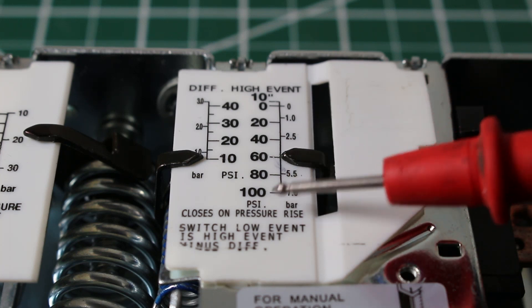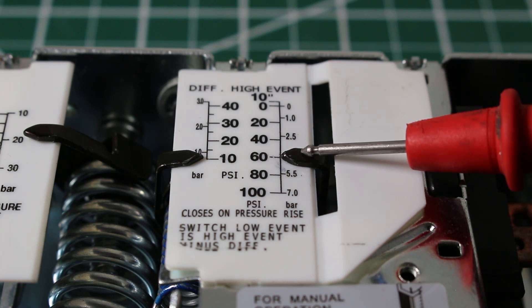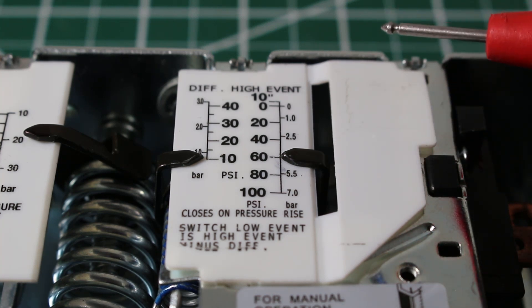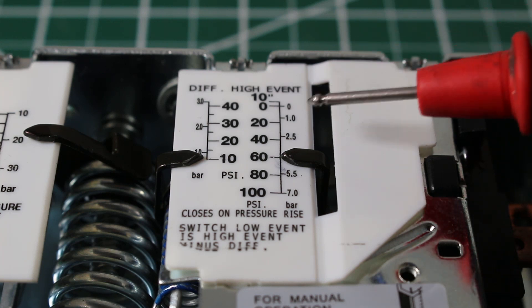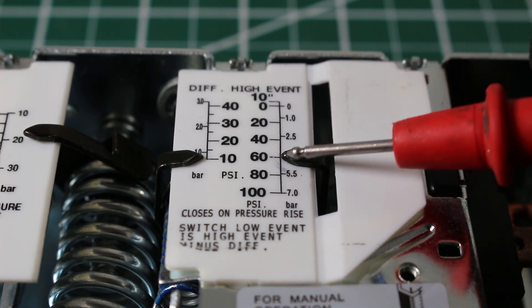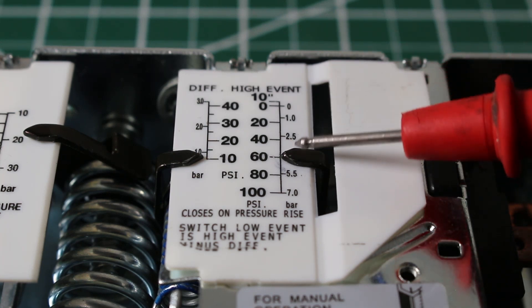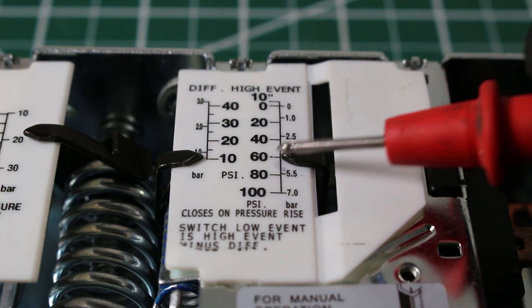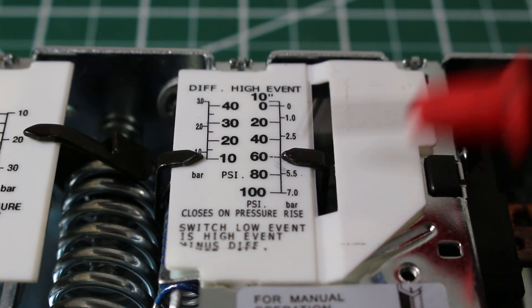But what is our high event? 60. So when the system shuts down, it's probably going to equalize in pressure. And when it equalizes, the system's pressure will rise. Once it rises back up to 60, it's going to come back on again. But if it happens to fall at 50, it's going to open again.